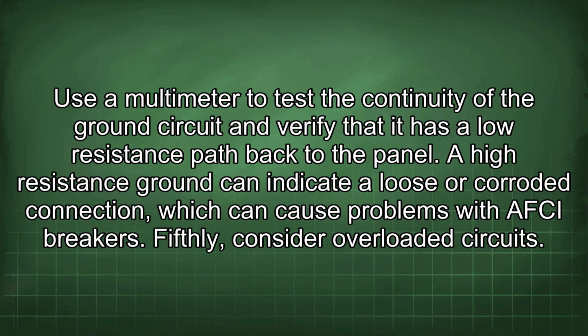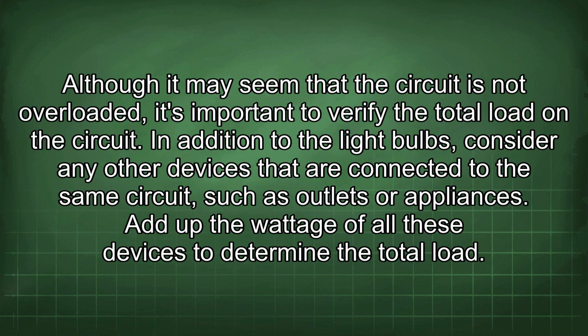A high resistance ground can indicate a loose or corroded connection, which can cause problems with AFCI breakers. Fifthly, consider overloaded circuits. Although it may seem that the circuit is not overloaded, it's important to verify the total load on the circuit. In addition to the light bulbs, consider any other devices that are connected to the same circuit, such as outlets or appliances. Add up the wattage of all these devices to determine the total load.